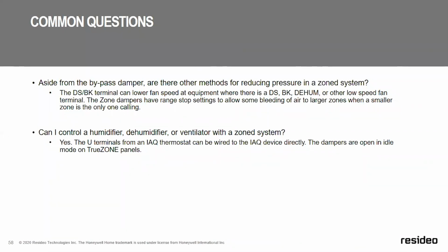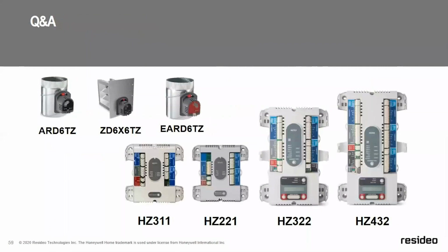And then finally, I'm going to go back to best case scenario, and then I'm going to look to make sure that it closed after I've adjusted it. If it doesn't close, then I'm just going to crank down on it just enough to where it closes, and then that will essentially be where you can stop. You can go back to your smallest zone again if you want to double check and make sure that it does open again.